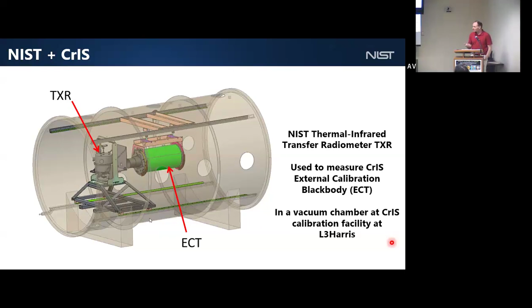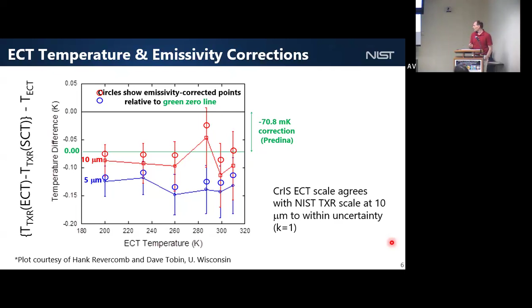So we can send a transfer radiometer to their facility and see how they agree. To make a long story short, because I was not involved in the taking of this data, they do agree to within their uncertainty. So that's some validation that not only is the device working properly, but that both their and NIST's estimates of the uncertainties of their respective devices are approximately correct.